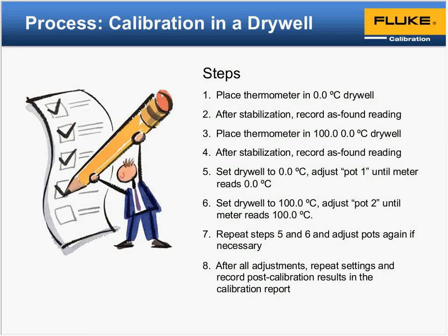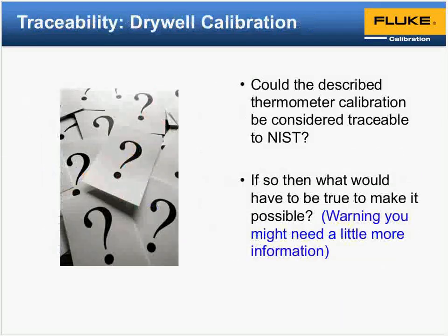Pros and cons with this one: you're basically going to get the best accuracy results, and that's simply due to the fact that we're using an external reference probe and readout, a magnitude better than what you're going to get from a reference or heat source display. Typically, with a readout and reference probe, the calibration that you're performing takes the heat source out of the equation as a factor other than simply being a heat source. Regarding versatility, you can get different reference probes in different shapes and sizes, closer to what you may have in the unit you're testing. So you can get quarter-inch diameters or 1/8-inch reference probes that give a better read on how they're actually performing in the environment under test.